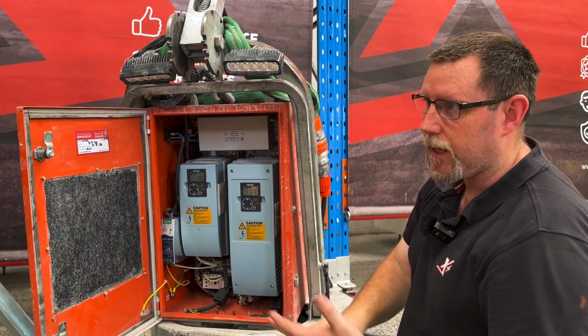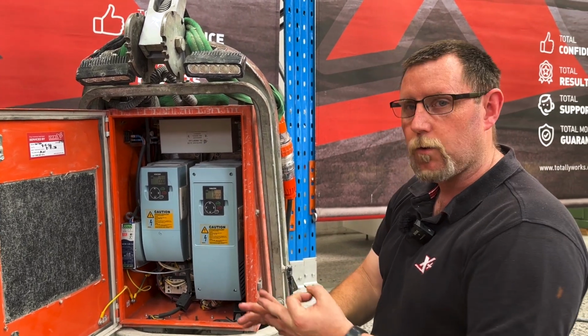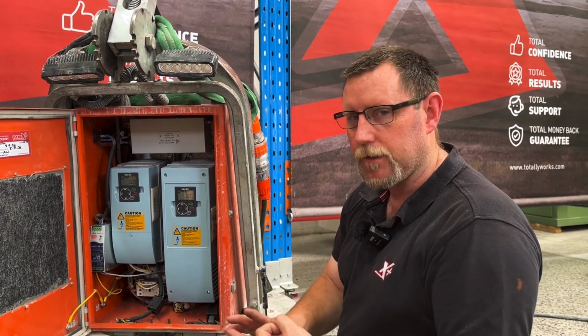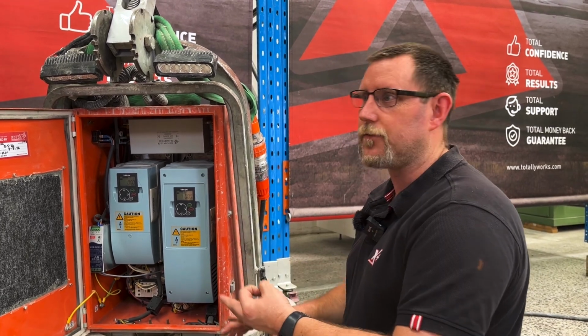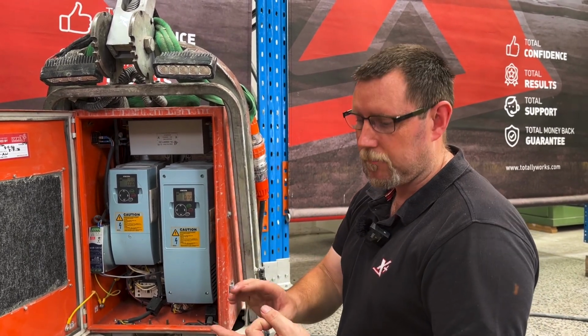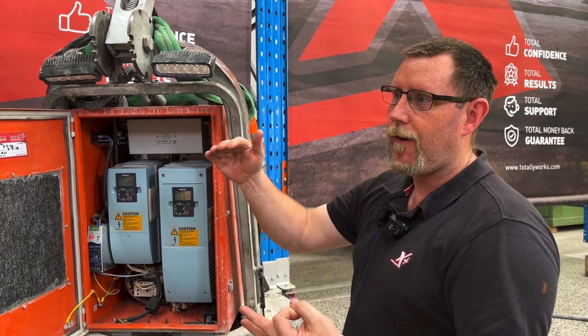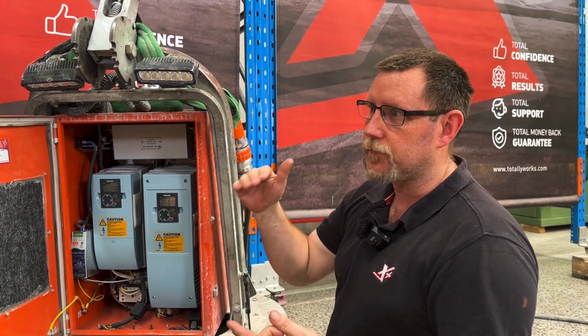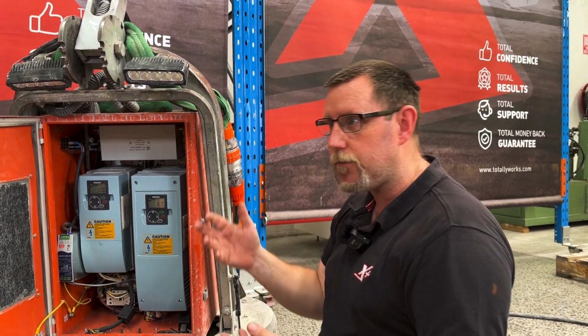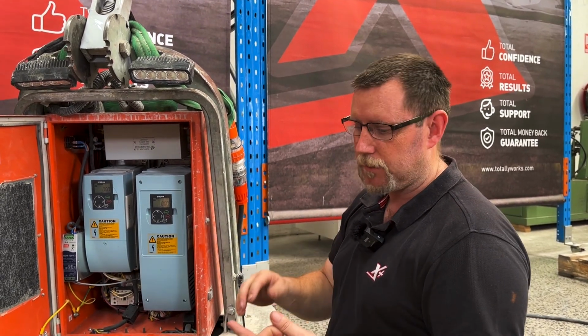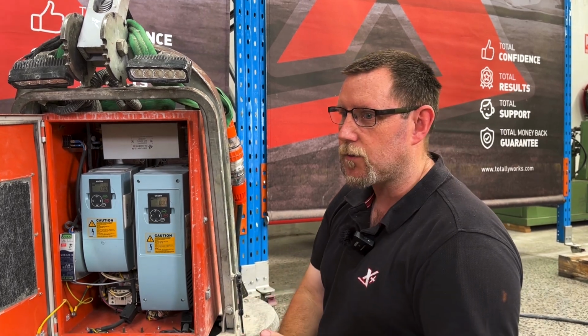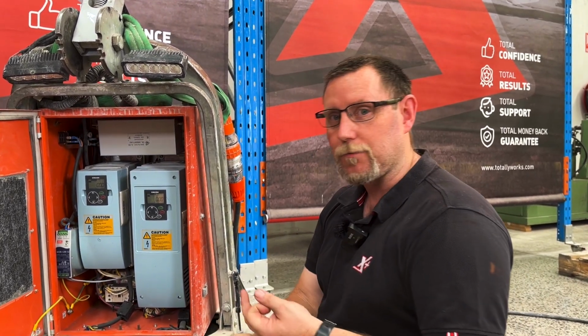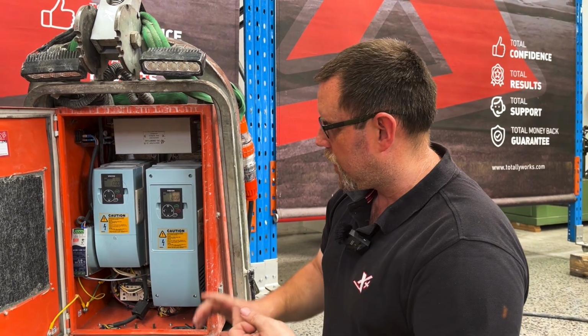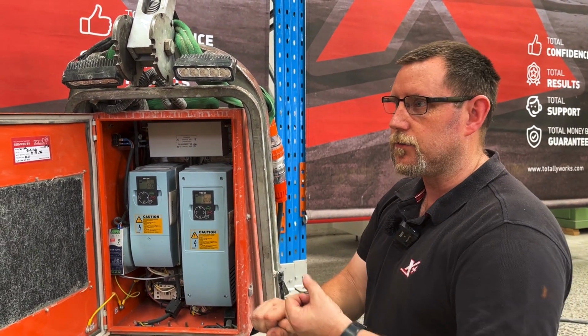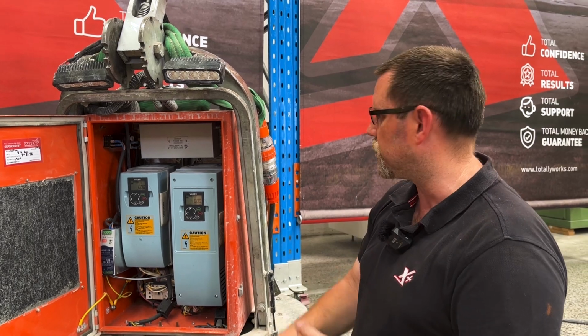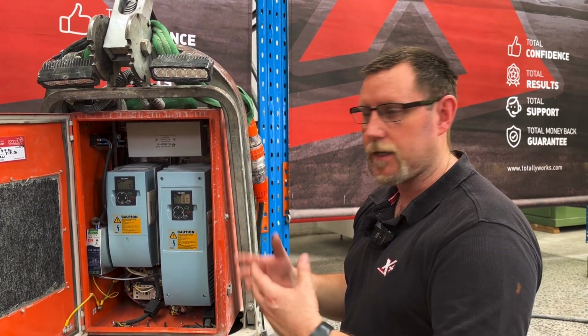We can go through and check all the amps, as Tim was saying. Usually we have three parameters we want to know, which we heavily rely on for both fault finding and performance. We want to make sure the machine is reaching the speed reference we're asking for, and that it's not under too much load - otherwise there's going to be other problems. We want to make sure it's not pulling too many amps, or that it's pulling enough amps from a performance aspect. So it's important to know how many amps you're pulling, to tell if the tool's working hard or working too hard, and then the machine's going to start playing up because it's hitting its current limits.